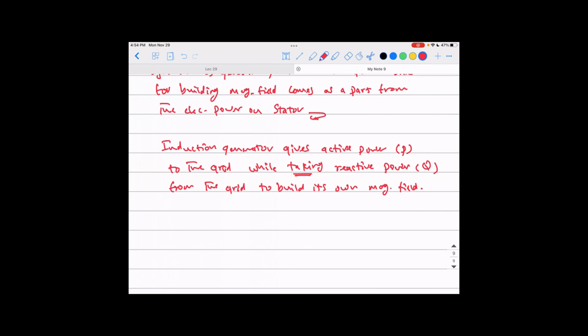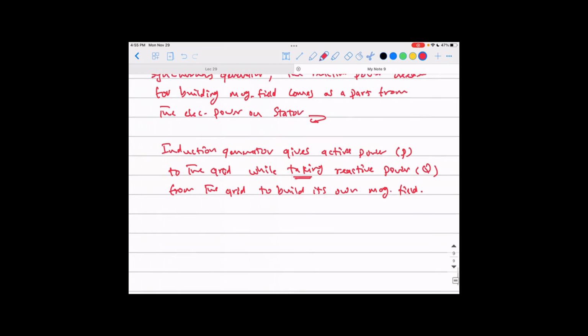If you remember, we talked about the synchronous generator before. It has a separate source that goes to the rotor, a DC voltage, to build the magnetic field inside the machine, and that's why this generator builds its own magnetic field, and it has an excess reactive power that it can push to the grid actually. For an induction machine, it does not have a separate winding, a separate source that goes into the rotor to build the magnetic field. So it has to get some electricity from the grid to build its own magnetic field, and then it gives back power to the grid. So the induction generator cannot provide the grid with a Q. Actually, it needs Q from the grid. While the synchronous generator is much better in this case because it can give P and Q, because it has its own source of building the magnetic field.